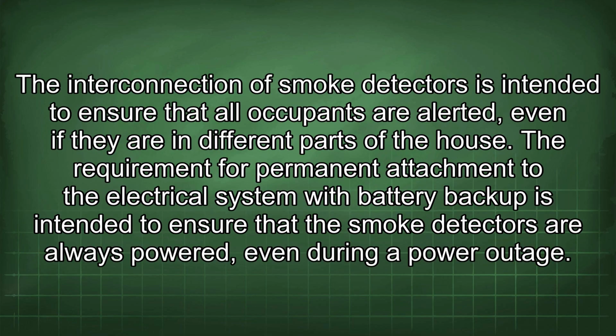The interconnection of smoke detectors is intended to ensure that all occupants are alerted, even if they are in different parts of the house. The requirement for permanent attachment to the electrical system with battery backup is intended to ensure that the smoke detectors are always powered, even during a power outage.